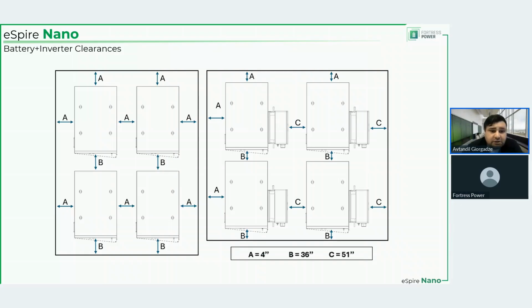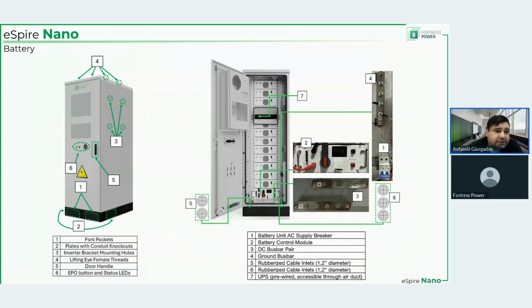Now, let's take a closer look at the battery. What do we get here? So we have 4 holes on top of the inverter. In those 4 holes, you can use lifting eyes that are included with the system. If you secure those lifting eyes in those female threads, you can use a crane to lift the unit. The unit itself, with the inverter on, can be around 2,600 pounds. So it's quite heavy. A crane is one method of moving it.